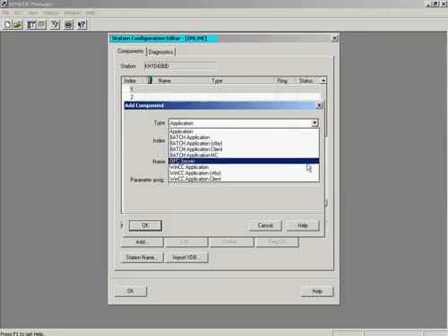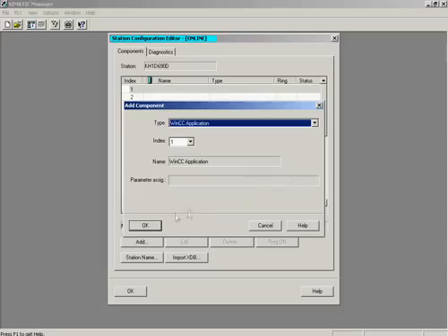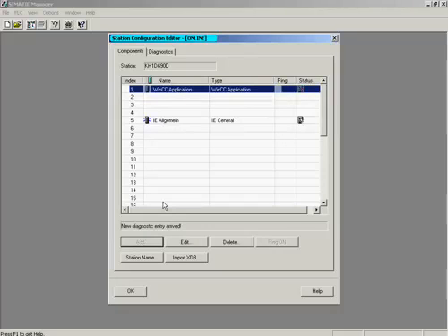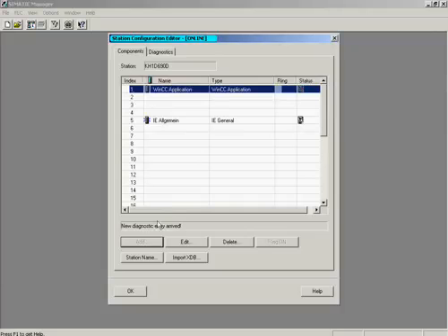A WinCC application is inserted. The objects can be entered at any position or index in the table. However, the indexes selected here should match the configuration of the computer, which will be carried out in the SIMATIC Manager. The Ethernet adapter has already been configured with the help of the Commissioning Wizard in Index 5. The computer configuration is now completed.